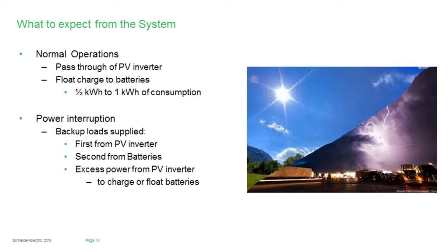And hopefully there's a very nice balance there. Let's say we have a 2-day power outage, and that system throughout the evening consumes power, and on the next morning, the batteries are going to be low. And so we need enough extra PV to actually charge the batteries while covering the loads inside the home. So when understanding how much PV to put into the system, we really need to make sure that we're sizing for daytime loads, and also sizing to cover some charging into those batteries as well, all the while making sure that we don't accidentally overcharge those batteries because we're pushing too much current onto them.